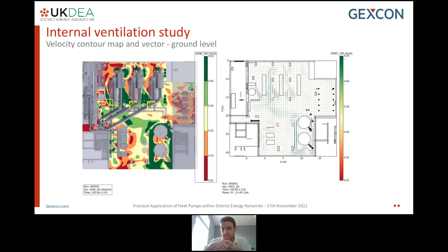The next step is conducting dispersion modeling studies where we try to test our detection system. The idea is to challenge the system by setting releases, based on actual process conditions, that point towards areas of reduced ventilation, which will have the effect of less effective dilution of the gas cloud.